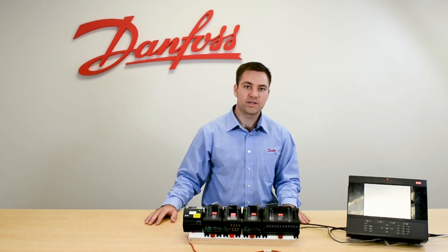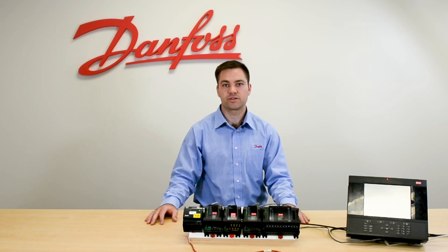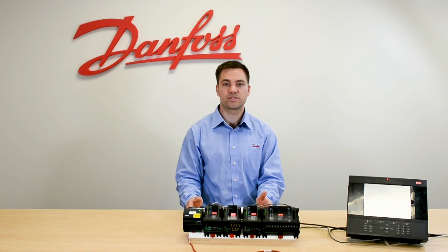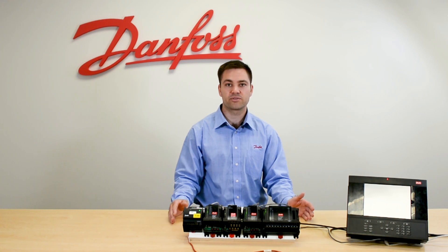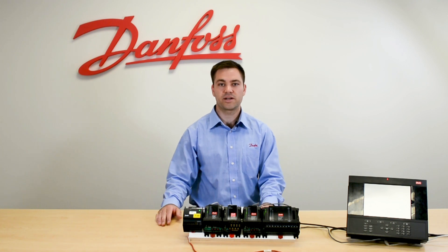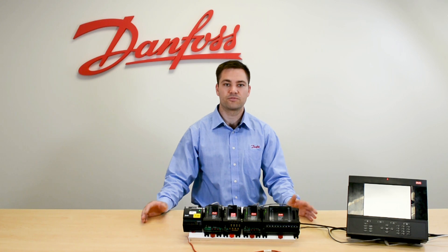These are RTD sensors, which means it's a resistance temperature detector, and they're very accurate over a large range. So compared to a thermistor which has a high accuracy over a small range, these sensors have a very high accuracy over a large range — from 32 degrees all the way up to a heating supply temp, and you can also go down to negative 40 degrees.